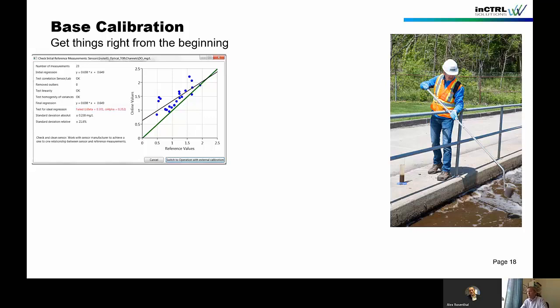In this case, all the blue dots are all over the place, and I have to admit we never really figured out what caused that issue. It's clear that a new calibration wouldn't help. However, that information was sufficient for the plant to say it's about time to buy new sensors. We did that, checked them, found them highly accurate, took them into operation, and everything was fine.